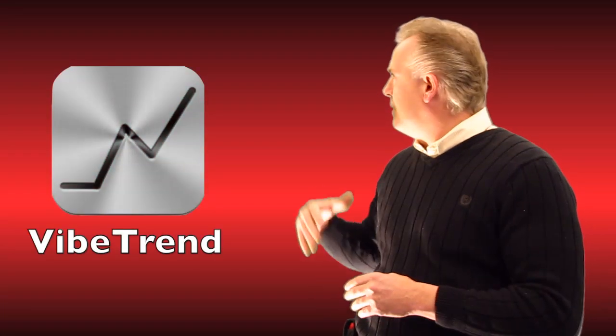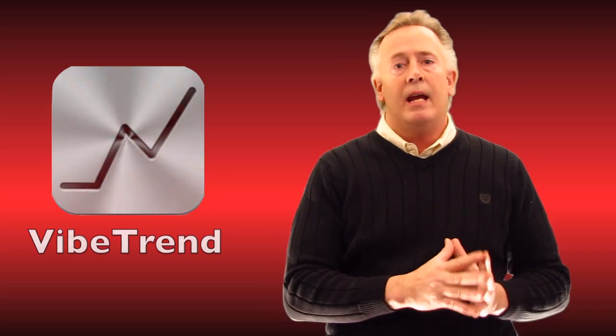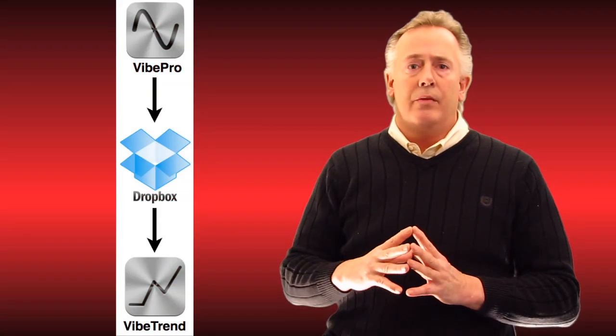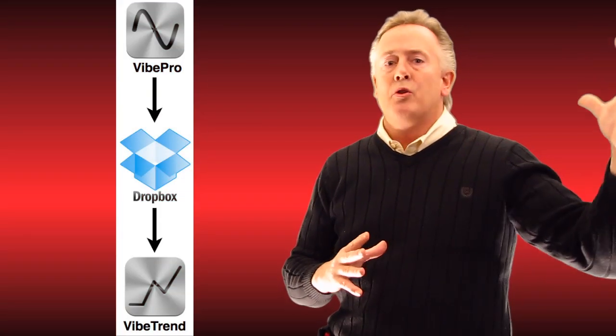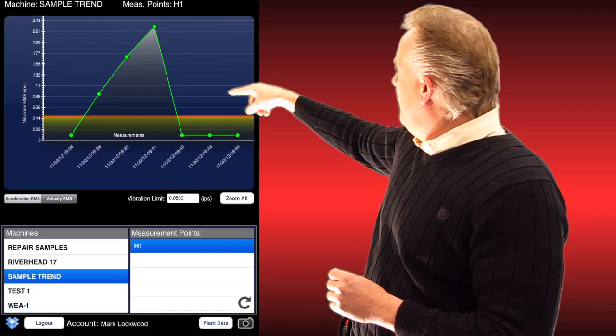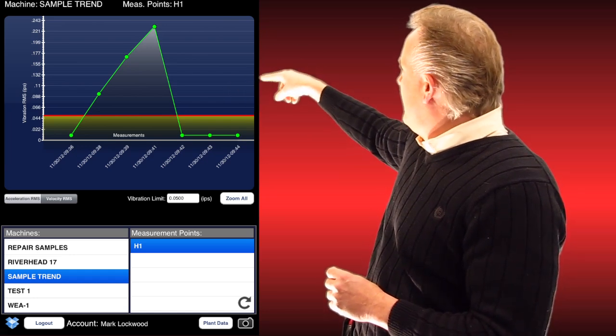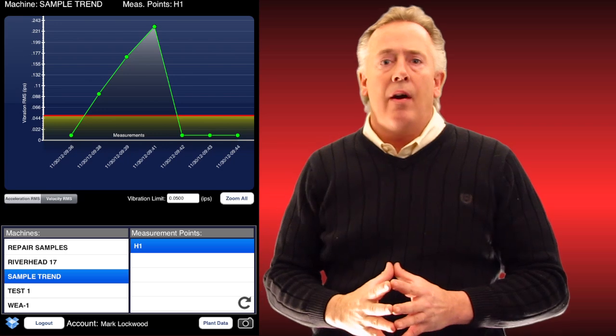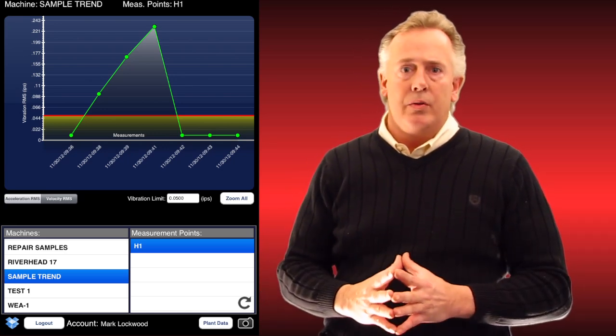I'd also like to put up VibeTrend, which works hand-in-hand with VibePro. VibeTrend pulls the data back down from the Dropbox cloud, and we're able to plot out a nice graph of where the data started and where it escalated as our assets degrade and get higher amplitudes in both velocity and acceleration. Very seamless way that we work our reporting and trending, all done up in the cloud so it can be pulled down at any time and observed through VibeTrend or Dropbox.